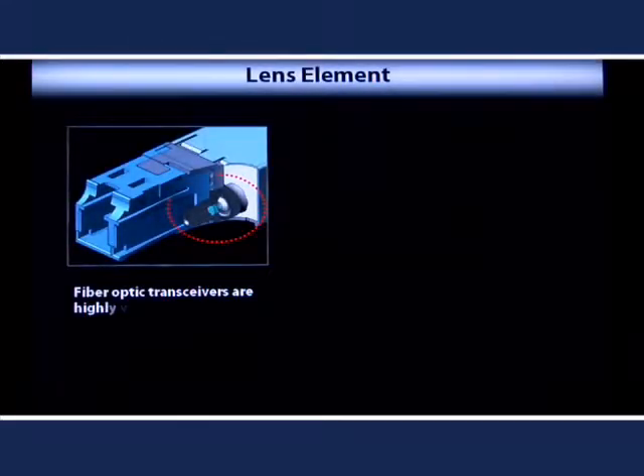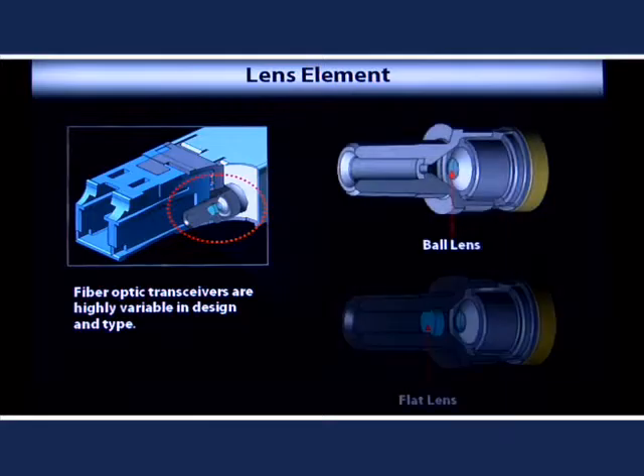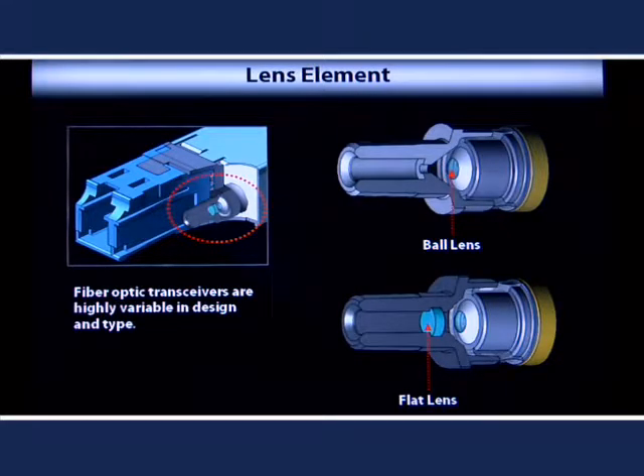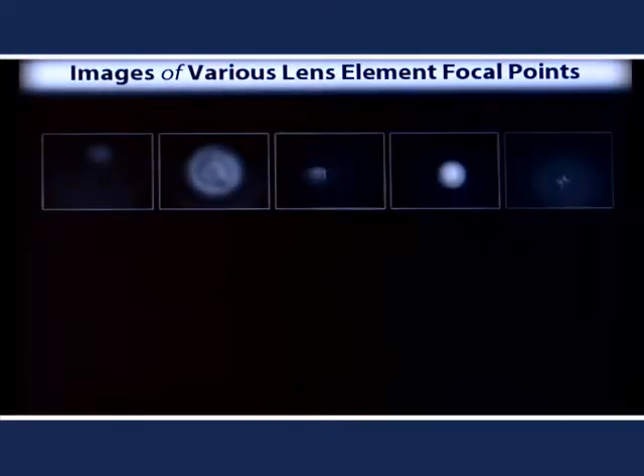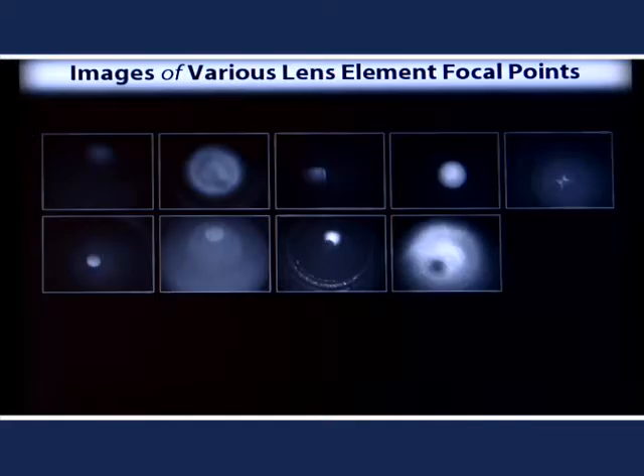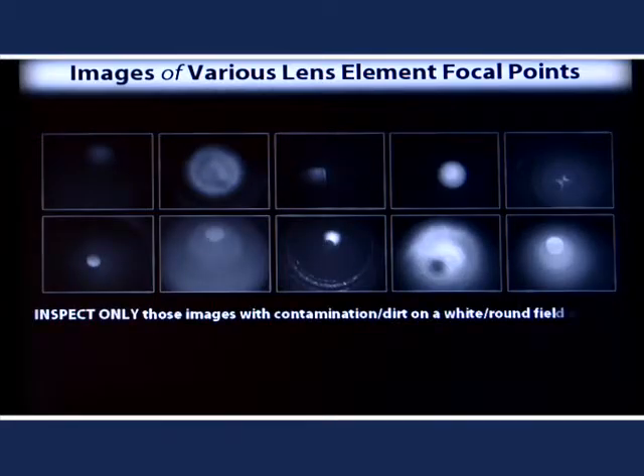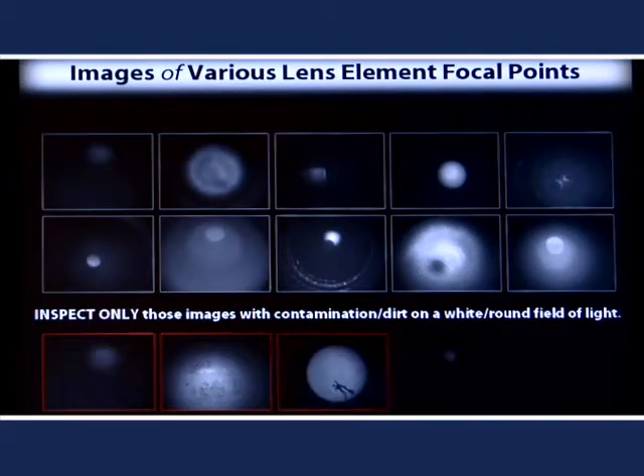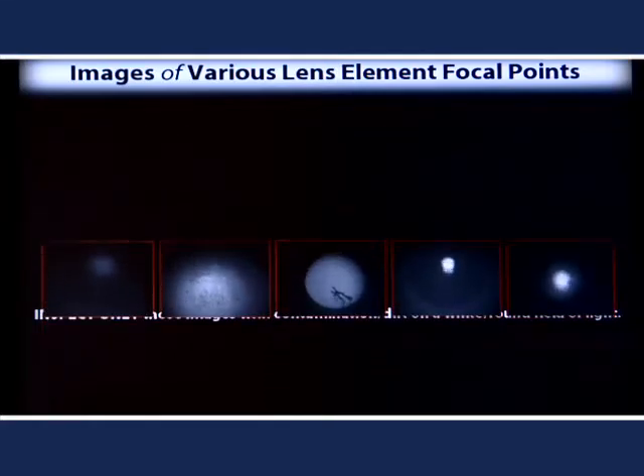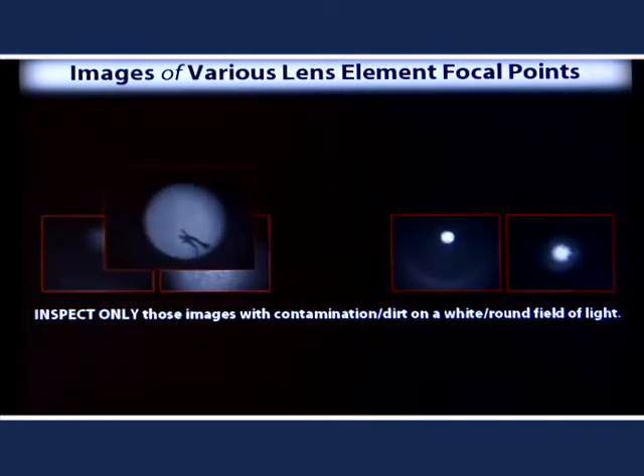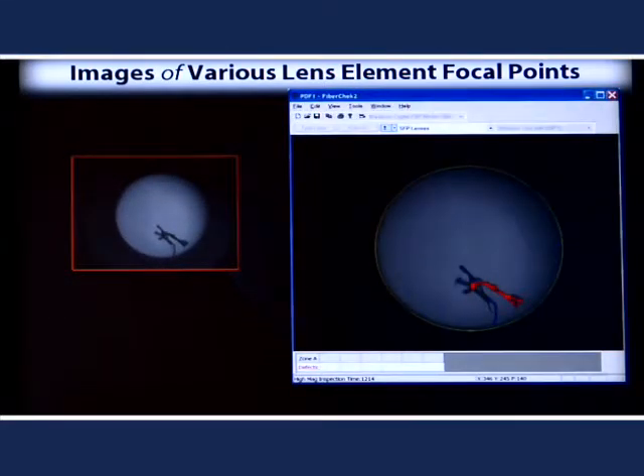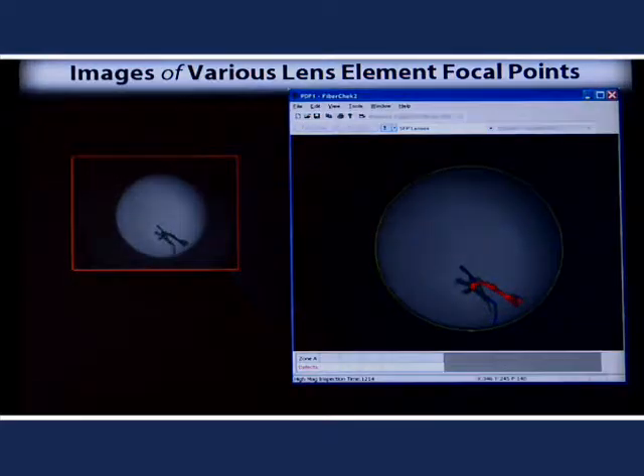If you focus inside this device and see an unusual image that is clearly not a simple fiber end face, you are likely looking at a lens assembly of some sort. These devices vary widely in design, and it is not productive to try and teach you how to discern exactly what you're looking at in each case. What is critical to understand is that you're looking for contamination on an otherwise round field of light. Let's walk through some basic guidelines for inspecting transceivers.